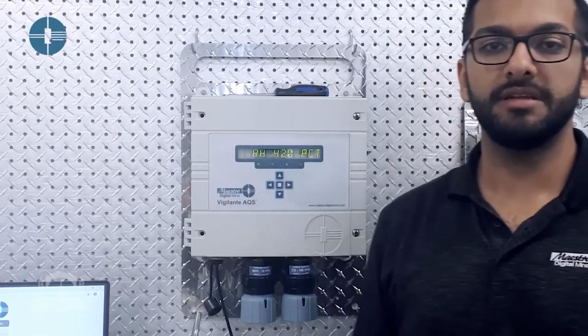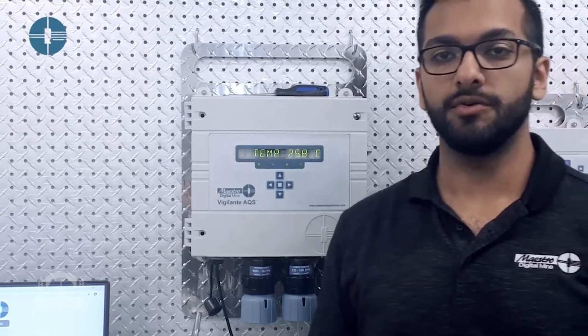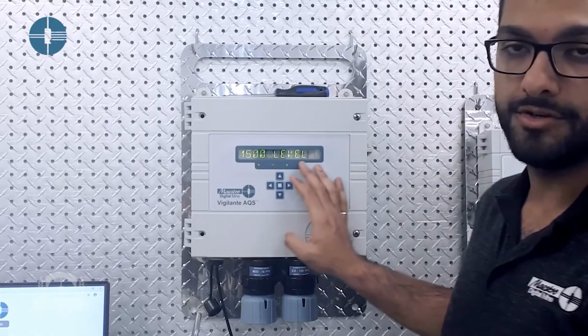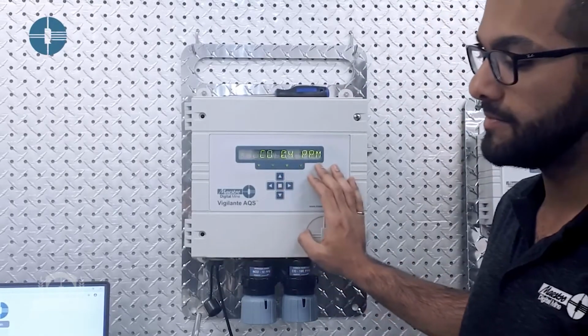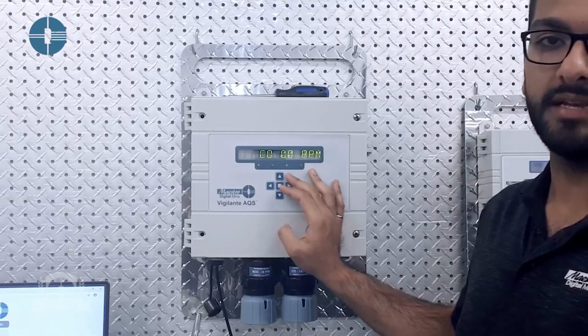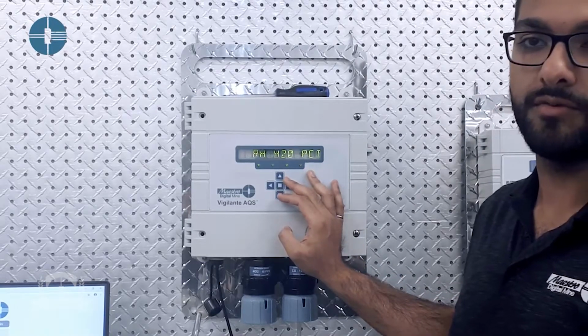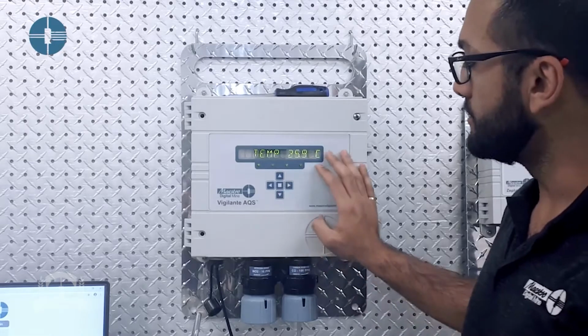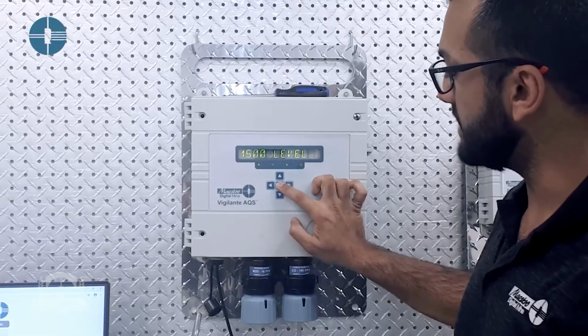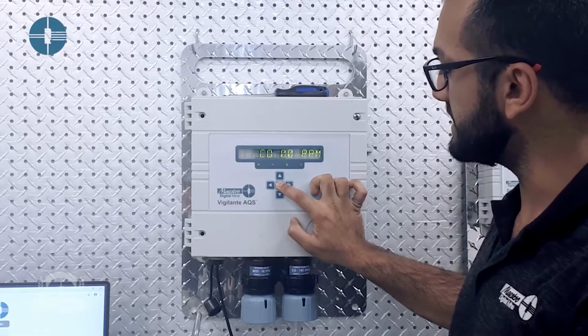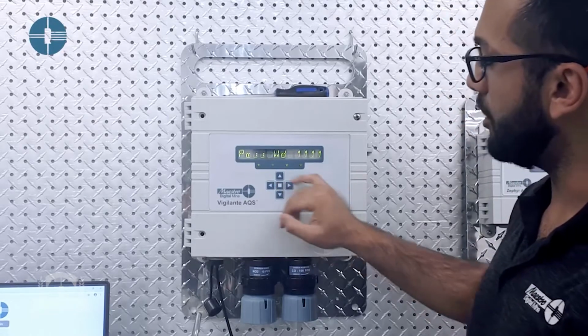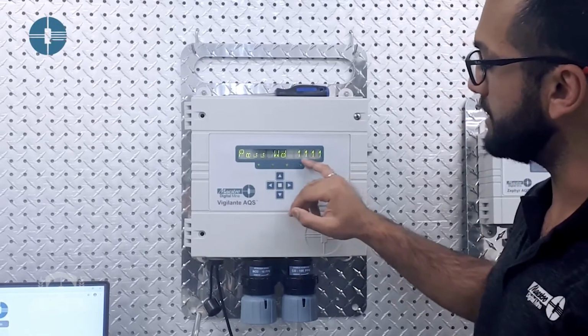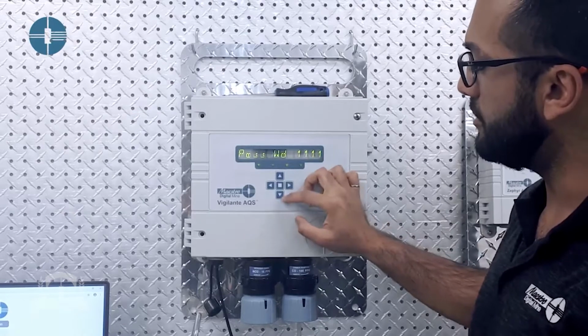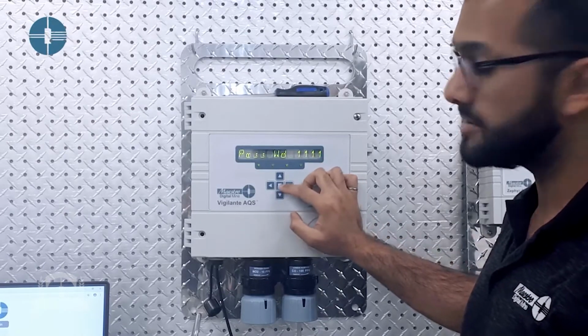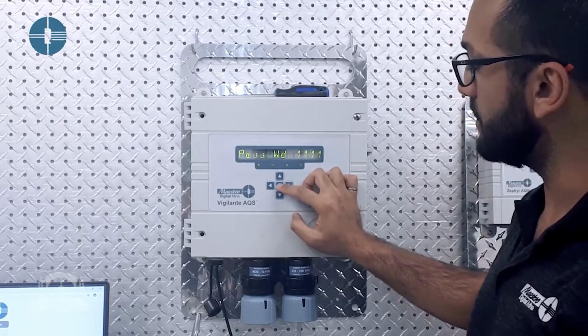So now that the 3 minutes have passed, we're going to go into a zero calibration using the front panel keypad. Now it's important to make sure that the front panel keypad is enabled. That can be done through the web page itself. So we start with holding the center button for approximately 6 seconds, and you'll get prompted with the password. Our default password is 1111. You can use the up, down, right, left keys to change through the password to whatever you've set it to.